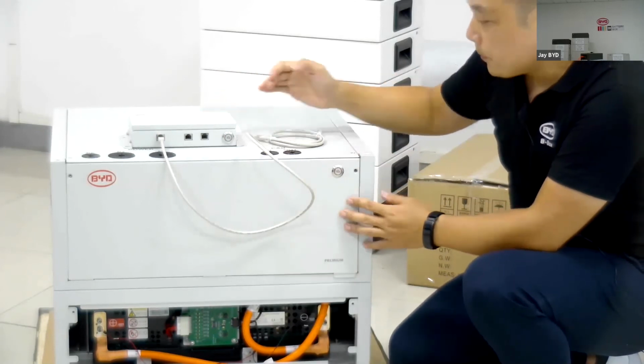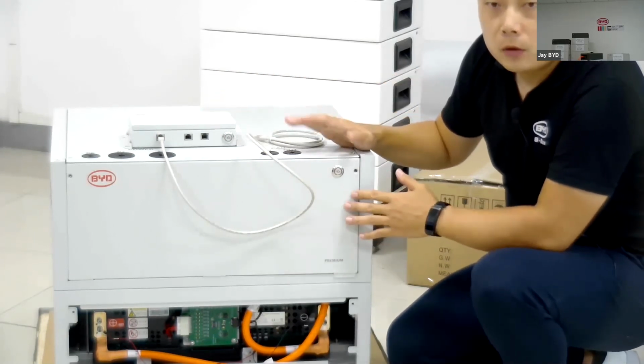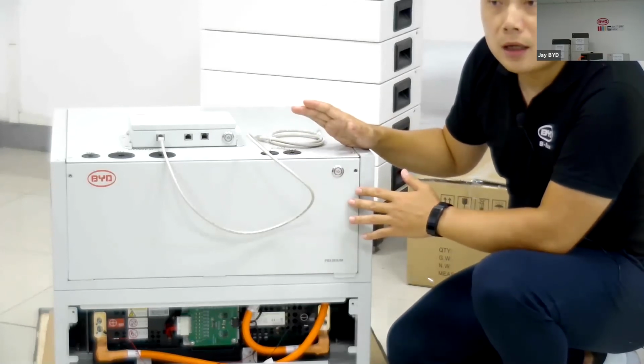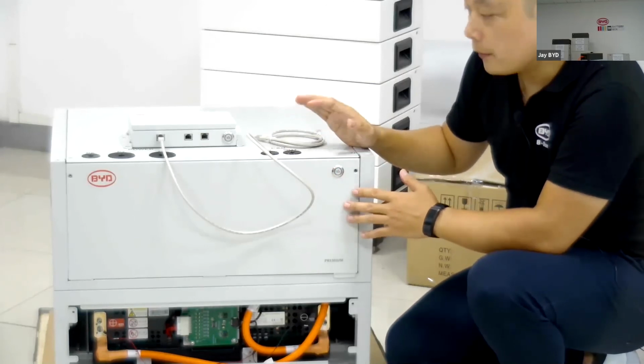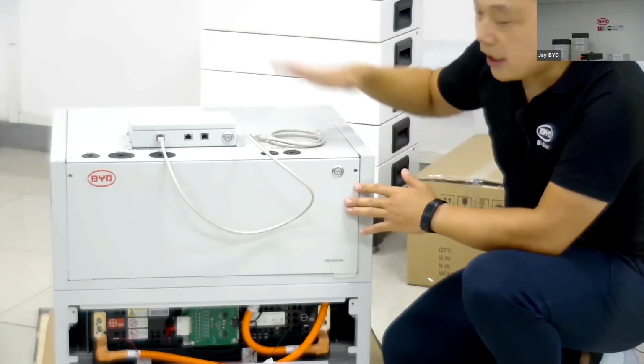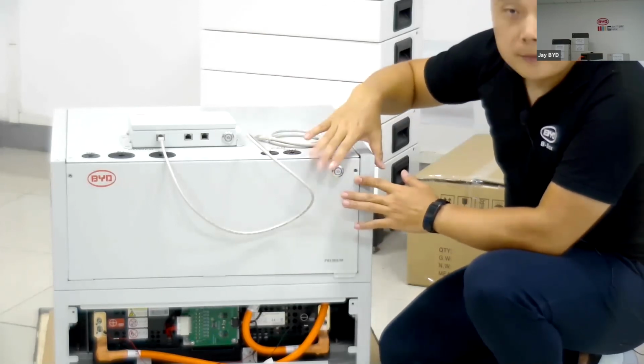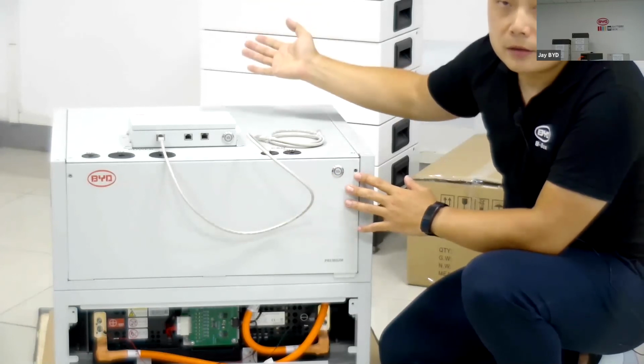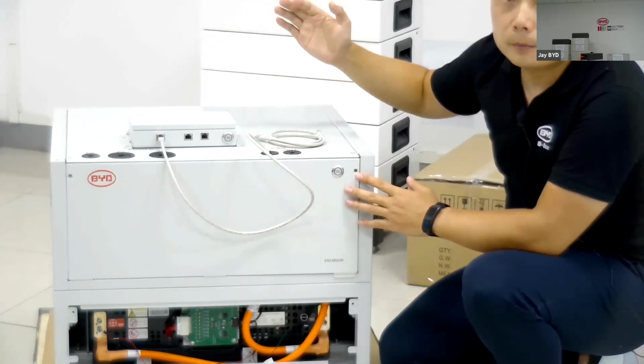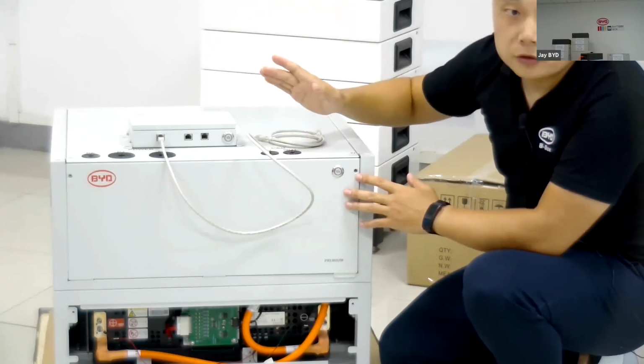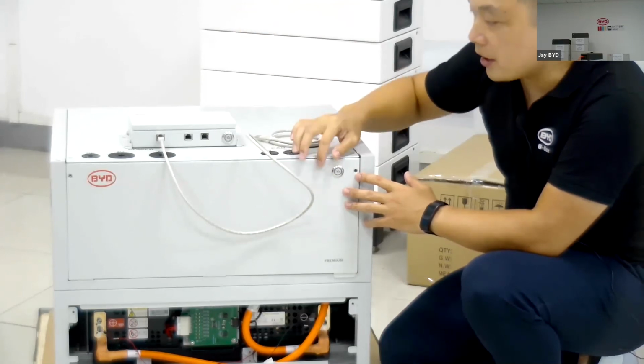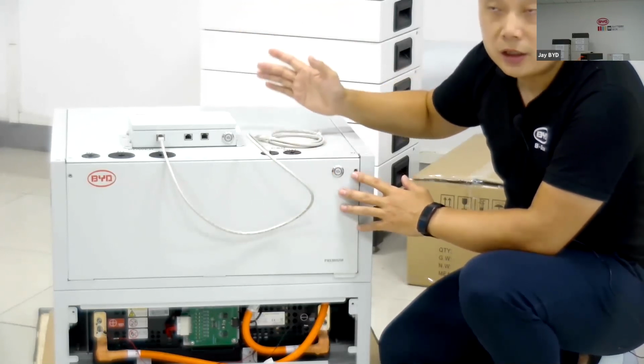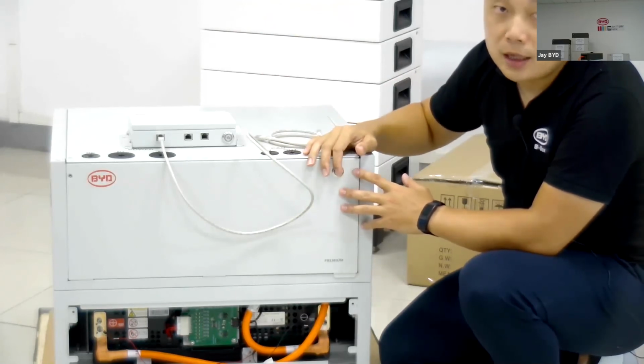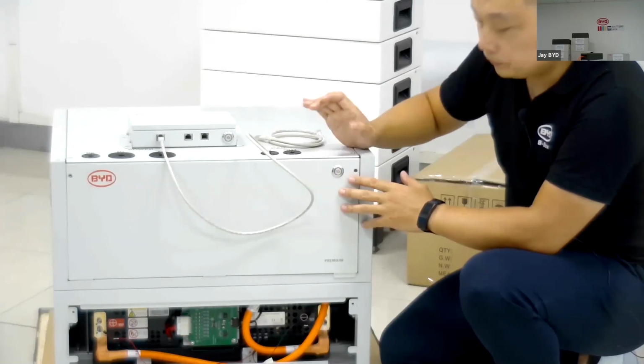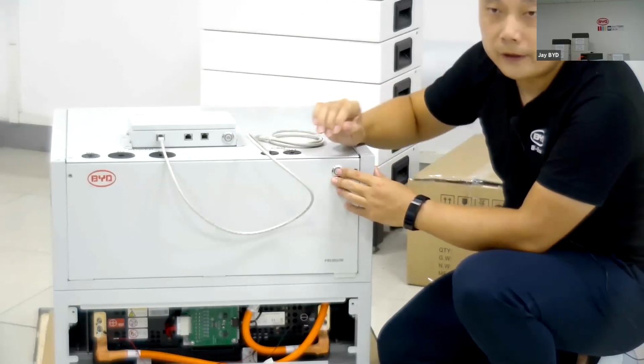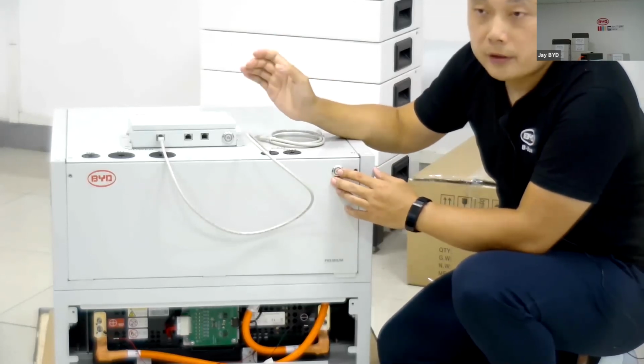In off-grid scenarios, the correct turn-on procedure is to always first turn on the DC breaker between the battery and the inverter, and secondly turn on the battery, then the inverter last. This is for the pre-charge circuit to work properly. If you forget to turn on the DC breaker first, the pre-charge function cannot work - the battery cannot pre-charge the inverter, and it may generate a short circuit alarm. In that case, just turn them off and turn on the DC isolator or fuse first, and the issue will be resolved.